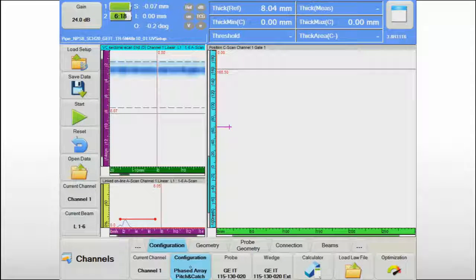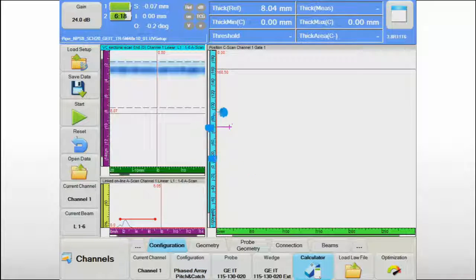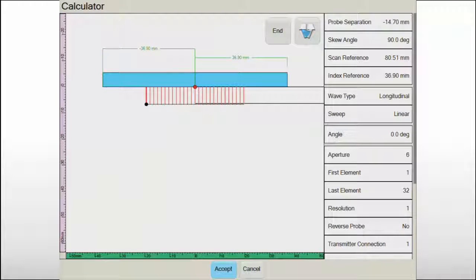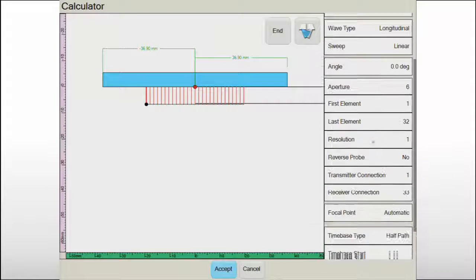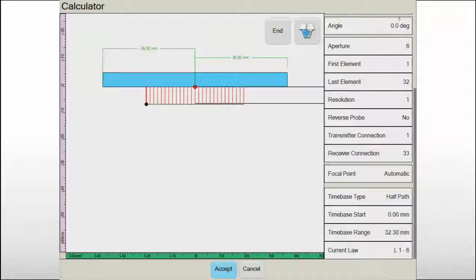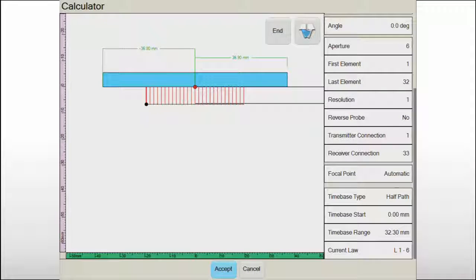The absence of an interface echo will improve the near surface resolution and the overlap of transmitter and receiver beams will improve the detection capability on small pitting corrosion.